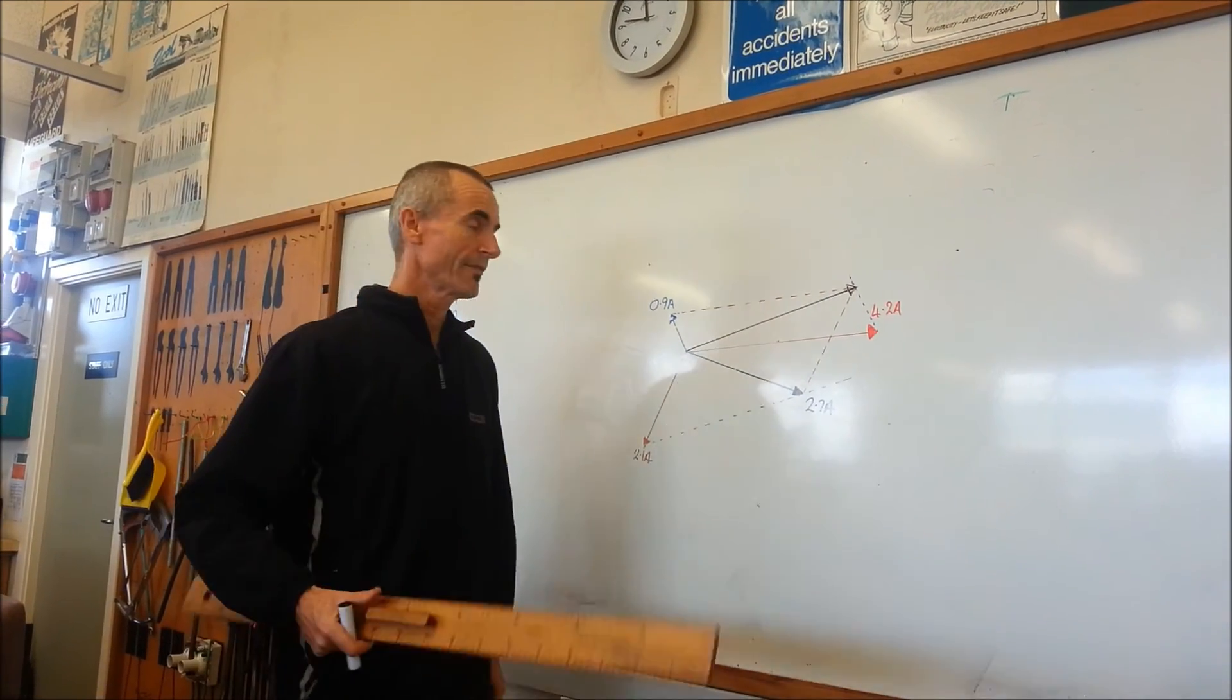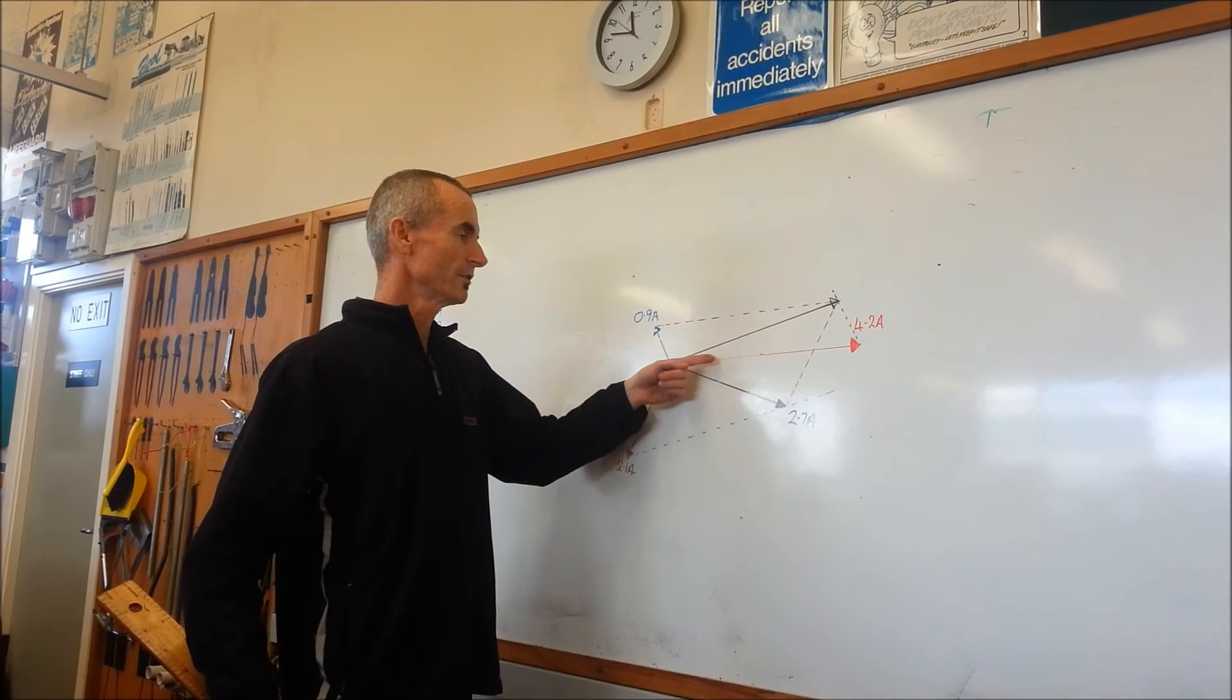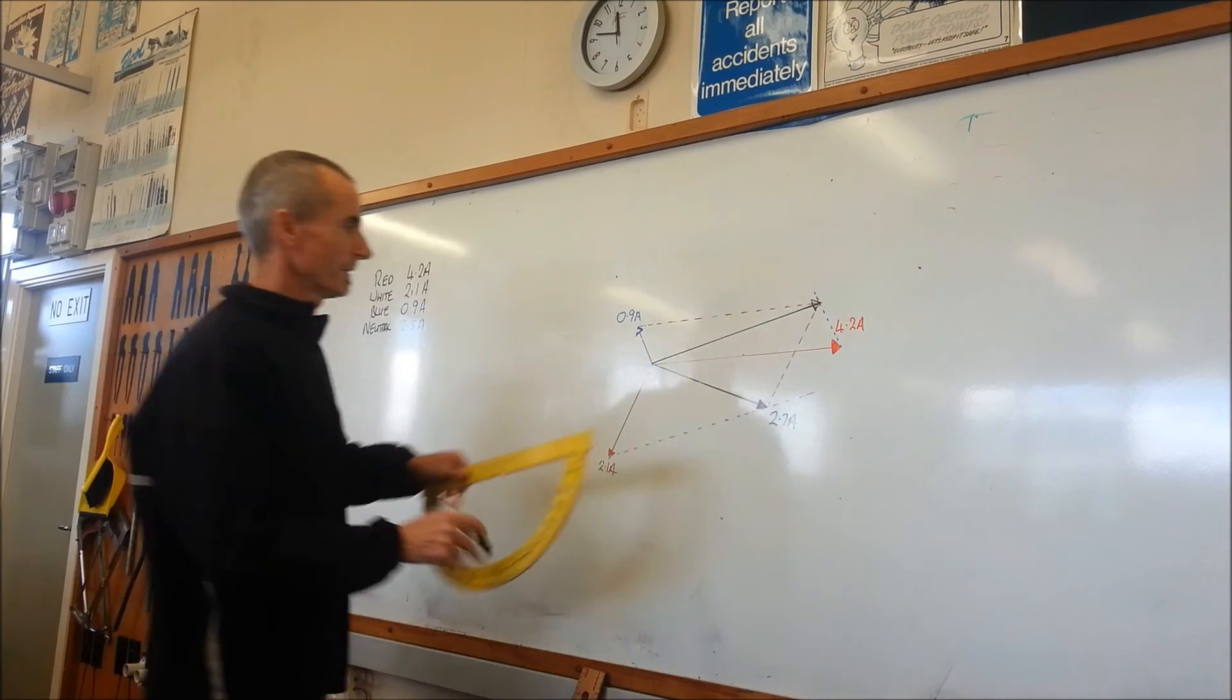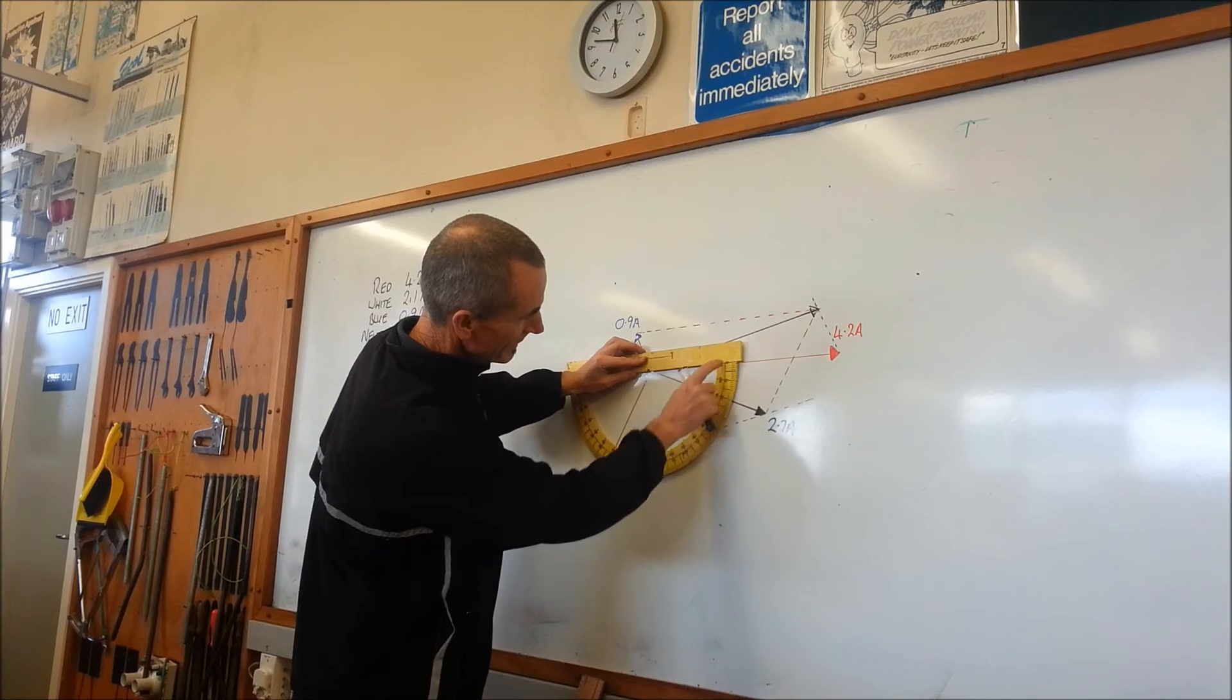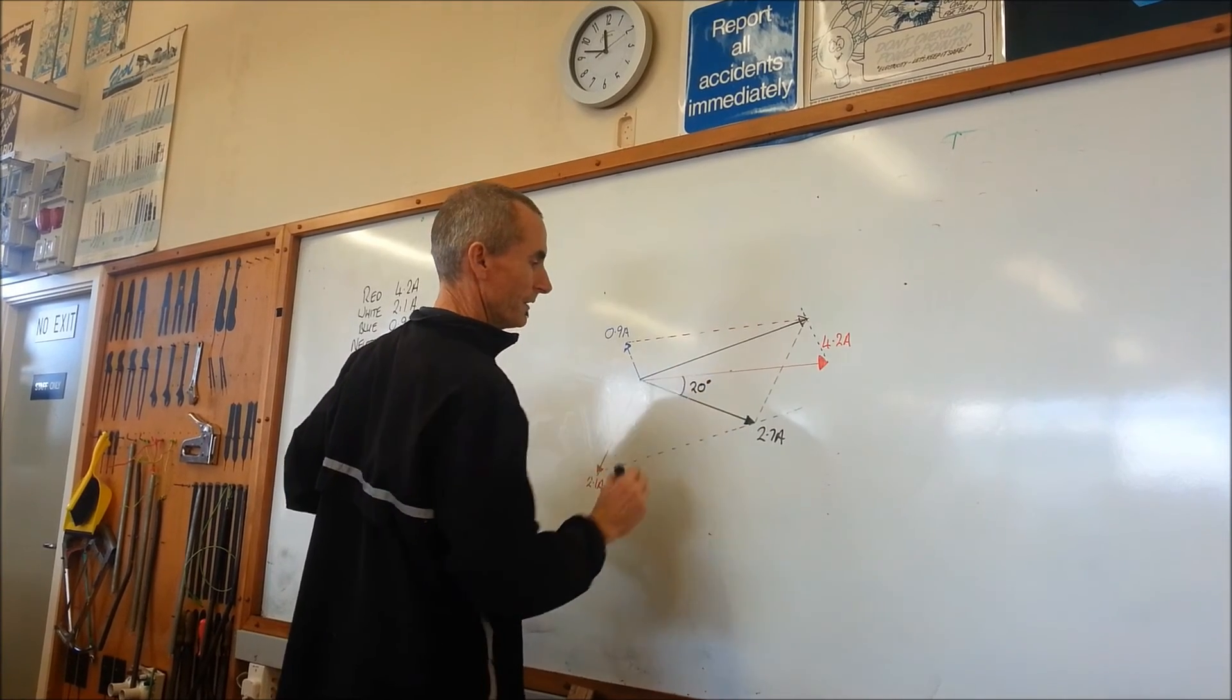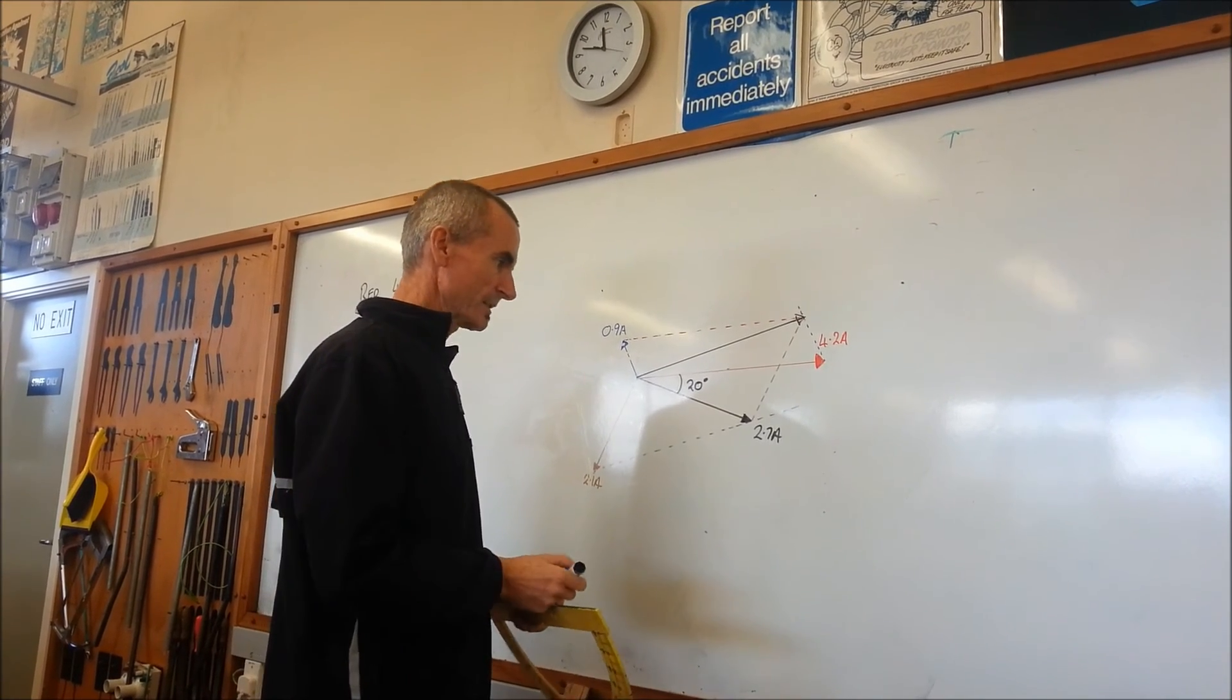Now we're left with the final part of this, to measure the deviation from any of the phases. The nearest phase we've got here, the neutral, the nearest phase is the red, so we can measure how far out that is. So from the red voltage it's 20 degrees. So from there you could say the neutral current is lagging the red voltage by 20 degrees and 4.3 amps.